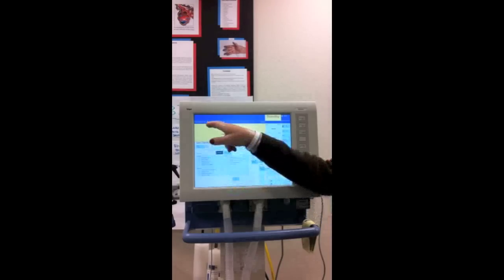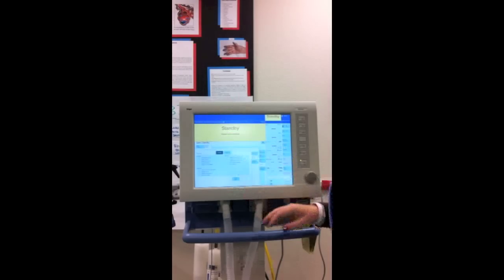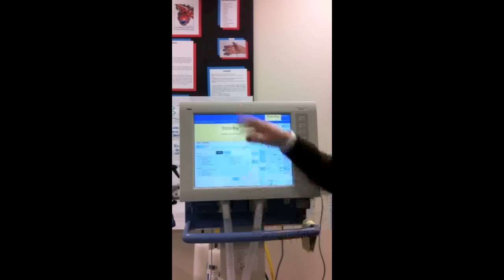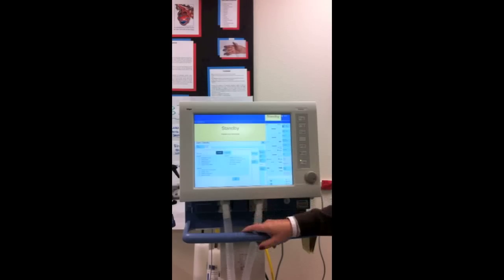Flow calibration, then it says calibration okay. So we know that's good. Disconnect, seal neo flow sensor, press button. We're going to do next test because we don't want to calibrate our neo flow sensor, because we're not using one. So it says aborted, which is okay. Now it's doing its O2 calibration.